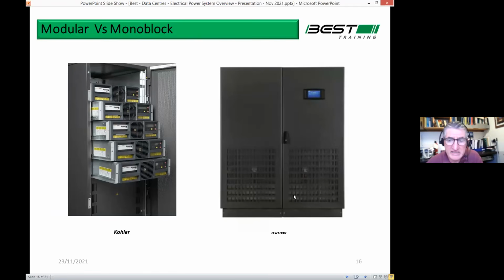And the other thing I suggested is monoblock versus modular. So the monoblock is what you see on the right-hand side, and it's sometimes called monolith, meaning the same thing, really. It's a big block UPS. So that, for example, on the right could be a 400 kVA UPS system. The one on the left could also be a 400 kVA UPS system, but just made up of individual modules. So you can see there's 1, 2, 3, 4, 5 modules. So each of those modules will be, let's say, I'll do it the other way around. Let's say it's 50 kVA, which is fairly typical. So that'd be 5 modules at 50 kVA, giving you a total capacity of 250. And the system on the right is 250 kVA.